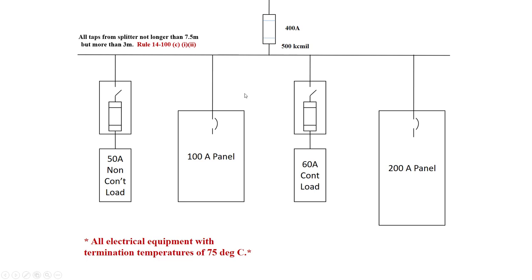As soon as we go over three meters but not more than seven and a half, this tap conductor or all of these tap conductors must have a minimum of one-third the ampacity of the feeder conductor. In this case, the feeder conductor is 500 KC mil.